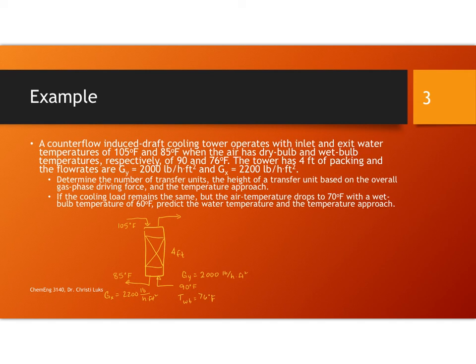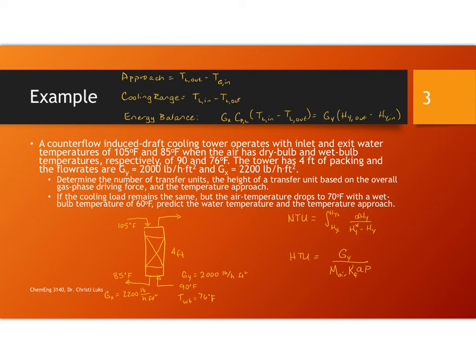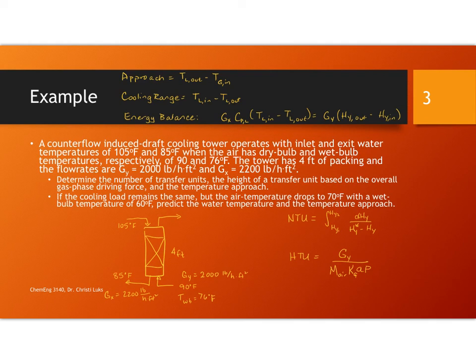Let me remind you of the formulas for these. We have the approach is the temperature of the liquid coming out minus the temperature of the gas coming in. The cooling range is the difference between the inlet and outlet water temperatures. Our energy balance is the flow rate of the liquid times C sub P for the liquid and delta T of that liquid, and that's going to equal G sub Y times the delta enthalpy for the gas. The signs are switched on these simply because it's going out of one and into the other. We have our formulas for number of transfer units and our height of a transfer unit.